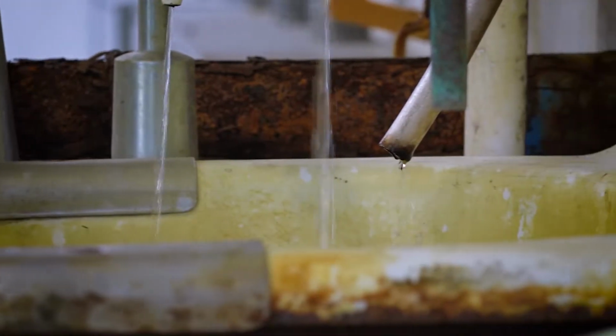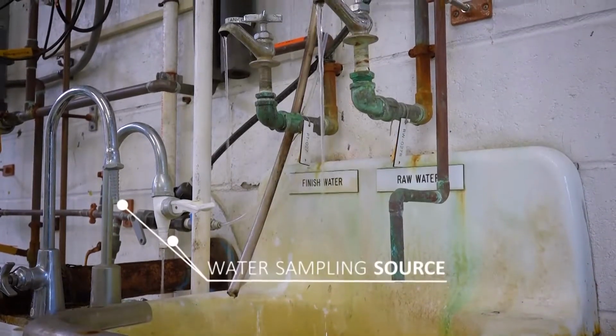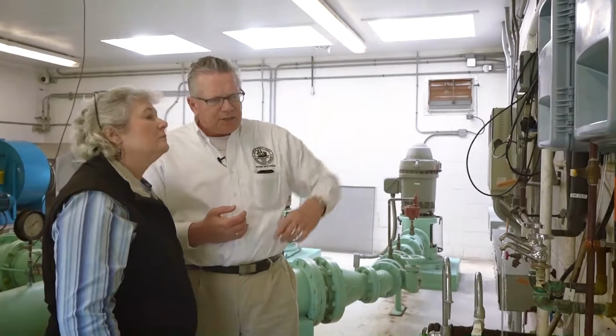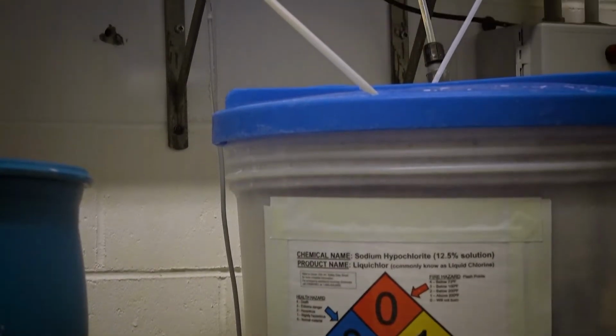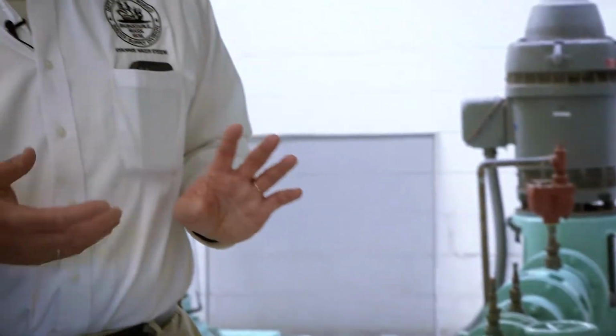There's two things. Those with the snouts on them, where the tape is off, are more for sampling. You take samples to make sure you don't get contaminated water. Those have to do with the analyzers. The chlorine and the pH, which is the corrosion issue, get sampled constantly, 24/7. How that works is we run water by them and then dump a little water that gets wasted. So we sample every minute or so, and that gets translated into an electronic pulse that goes into the system that we just saw, that screen, and then it goes to the main headquarters.